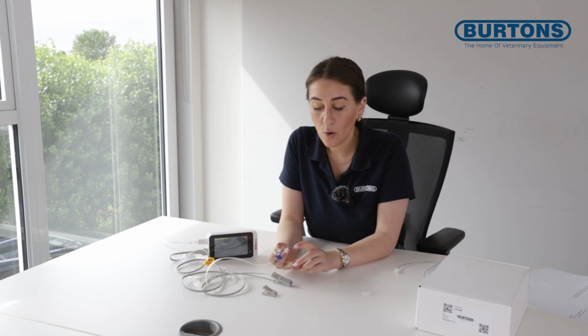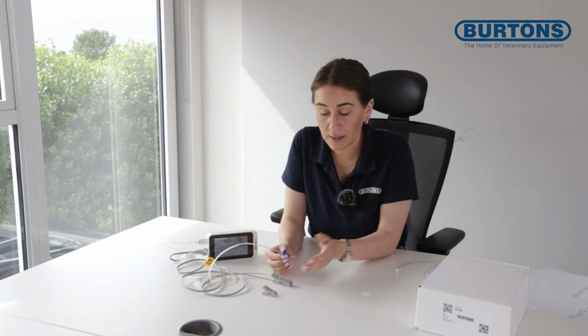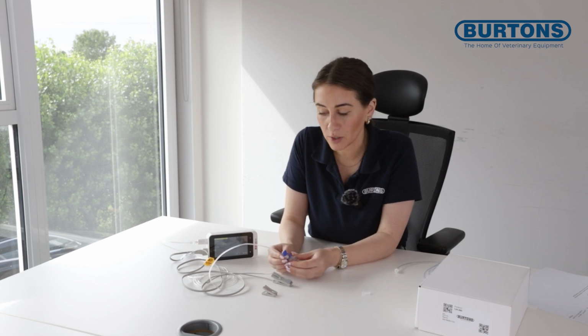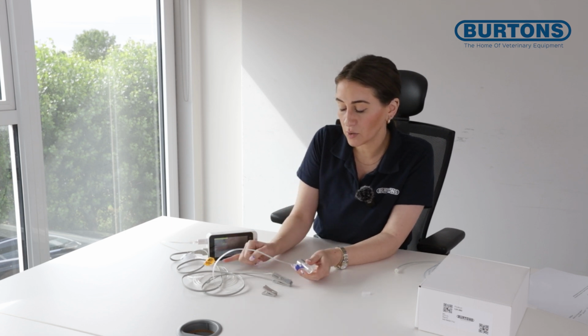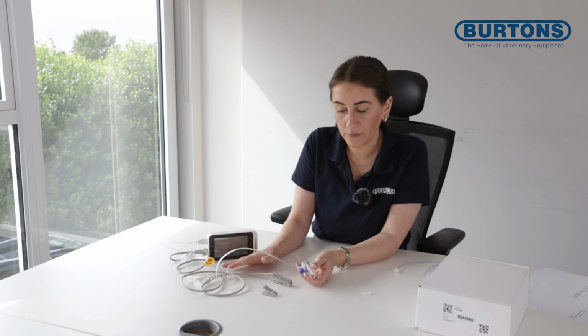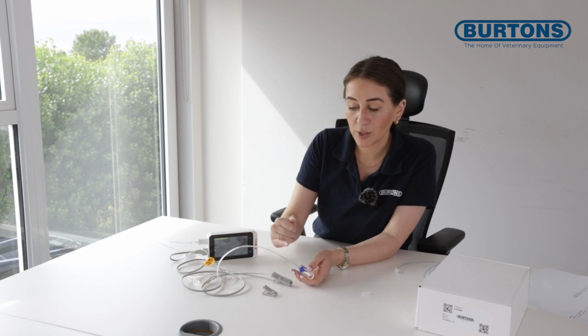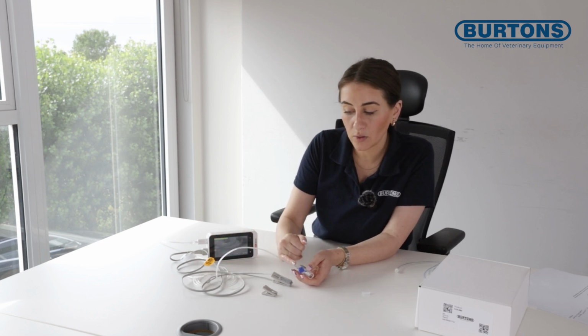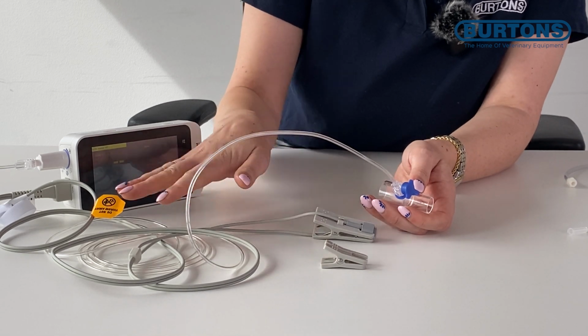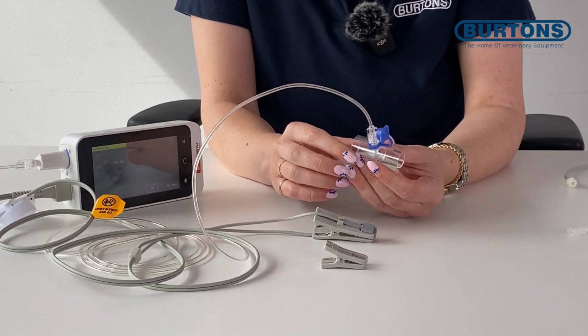High end tidal or high fractional inspired CO2 would indicate that there's an issue either with a low fresh gas flow or an exhausted soda lime, or for example a blocked scavenging valve as options for that increased FiCO2. We typically don't get issues with high CO2 as a result of any issues with the tubing. Potentially low end tidal CO2 could also mean that we have issues with the sample line becoming saturated with water vapor.